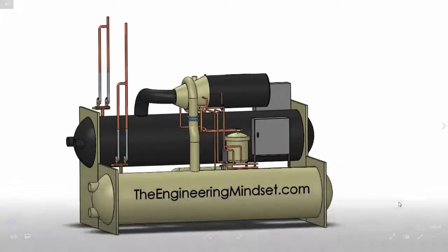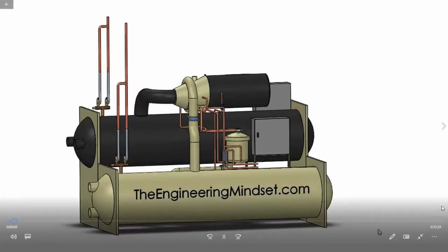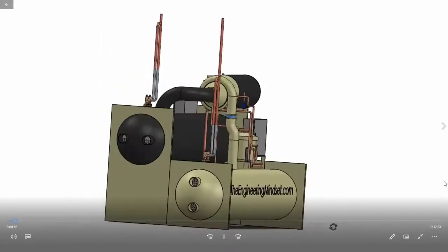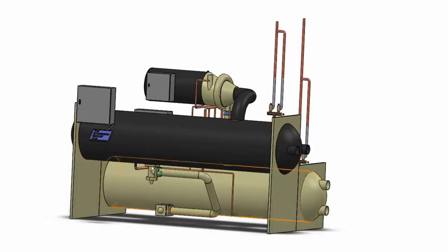Hey there guys, Paul here from theengineeringmindset.com. In this video we are going to be looking at the thermal expansion valve on a chiller. Now the expansion valve is located between the condenser and the evaporator, and in this version it is located just here. So in this video we're going to look at the three most common types of expansion valves in typical modern chillers, that being the pilot operated thermal expansion valve, the thermal expansion valve, and also the electronic expansion valve.